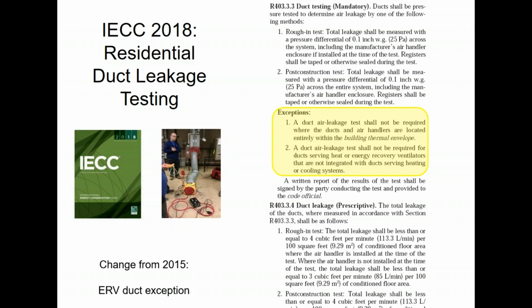Ductwork only has to be tested if it goes outside the envelope. And that's if any of the ductwork goes outside the envelope. So if you have everything inside the house, all the ductwork's interior, and then for whatever reason you have to jump up into the attic, go down 6 feet, and then jump back down into one of the spaces, because you did that for that 6 feet, you now have to pressure test all of the ductwork. So it makes it a little bit more work, obviously. They want you to put it all inside the building. That way, if it leaks, it at least leaks into the house. Granted, you won't get the right cooling and heating in the right room, but at least the energy's in the house somewhere.